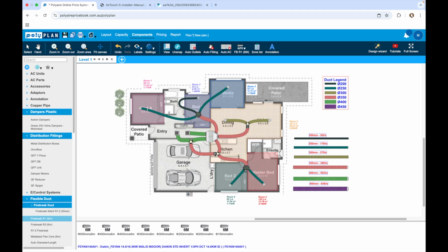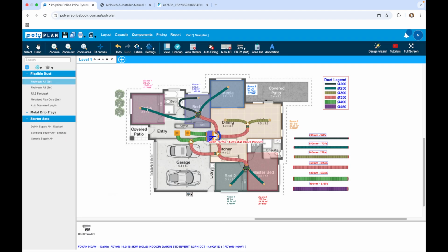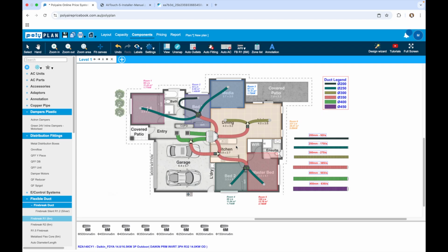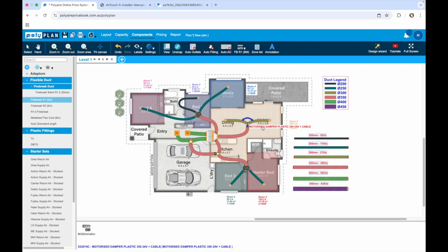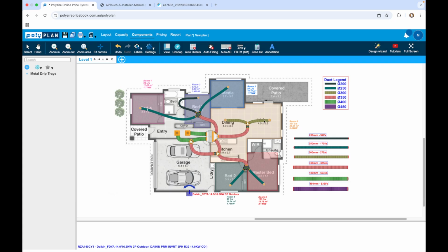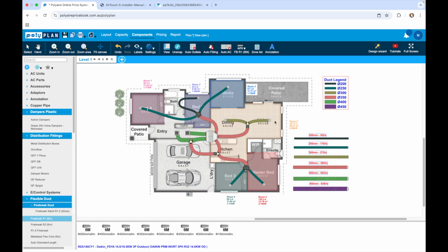The process of this opening and making this stop happens much faster and much sooner than what it would if this started opening and started dumping cold air into here and this unit kept running flat out to try to cool this area down. All of that little spots where that would be happening are gone, and that's basically energy you're saving, and it's comfort that you're getting back, because if someone wants to be 24 in here, it'll be 24 in here.